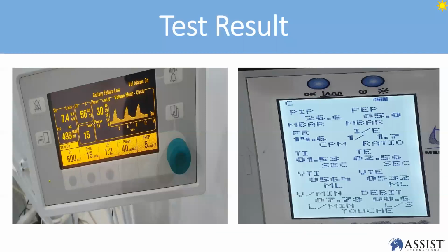So this is how the test results look. You can see your tidal volume. You can compare the results, VTI, VTE, and you can compare the breathing, 12, and you get the same reading line. So the breath rate is 15. Here is FR, the breathing line is 14.6. So it's almost the same reading. This is how you compare your readings and write them on your checklist.